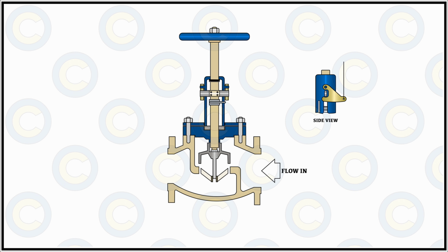Now, another important step that we often forget is that during the resetting of the quick closing valve, we first have to close the entirety of the valve. So basically what that means is that before opening the valve with the help of rotating the disc counterclockwise, we first have to rotate it clockwise and close the valve.